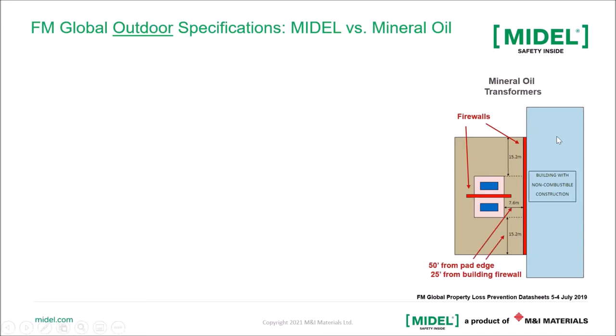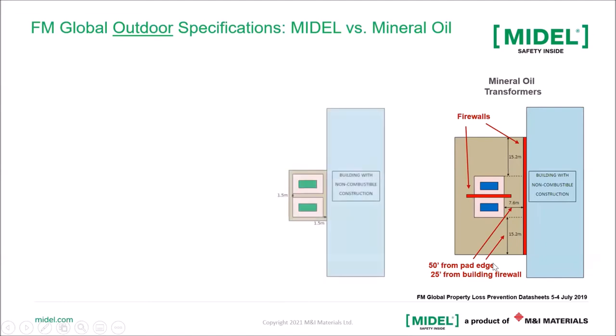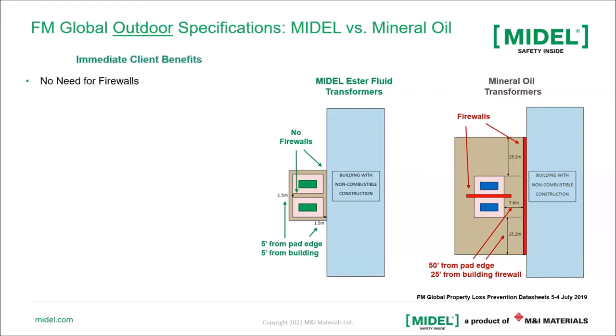So what you're seeing here is that there's a building, there are two transformers, and between the building and the transformer, there's a firewall, as well as a containment here, and there's 50 feet distance from the pad edge and 25 feet distance from the building firewall. Now, on the other hand, when you look at a MIDEL ester-filled transformer, there's no need for a firewall and the distance has significantly been reduced to 5 feet from the pad edge, as well as from the transformer to the building. If you notice, the containment here is much smaller as well compared to what it would be with mineral oil filled transformers.